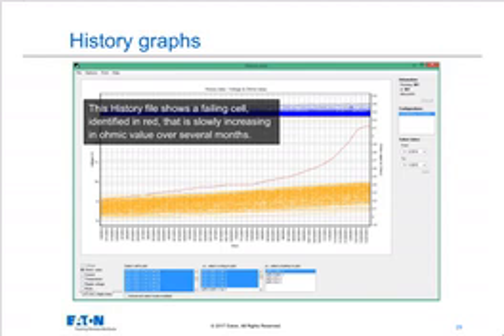I think the next slide has a similar graph here showing the history. And again, we're looking at a lot of batteries during quite a few months of their service life. And you see the orange area at the bottom of the chart is sloping upward over time. And basically it's showing that over the aging process of the batteries, it is common or normal for the impedance to rise slowly over the 5 to 7 year service life in a UPS application. If the impedance rises quickly, like the one red line that you see there, that's evidence of a failing cell.